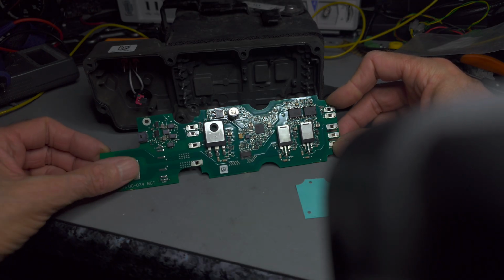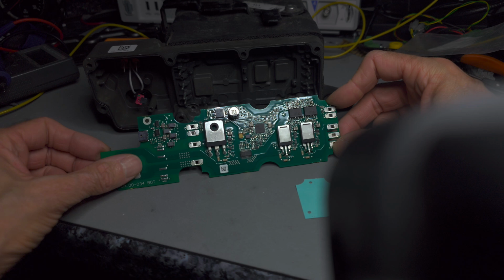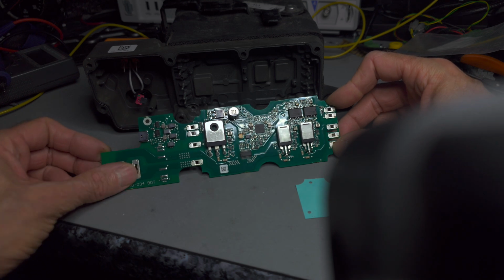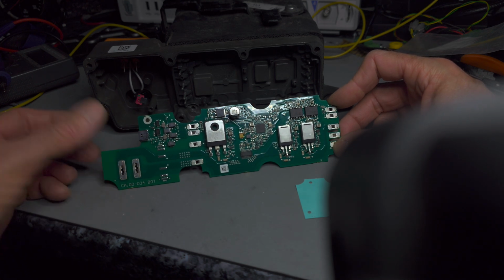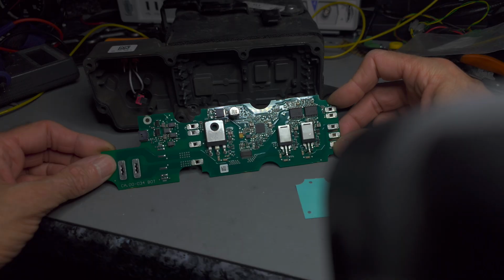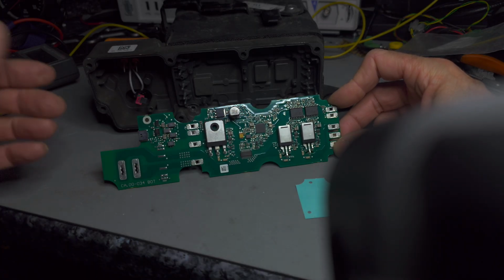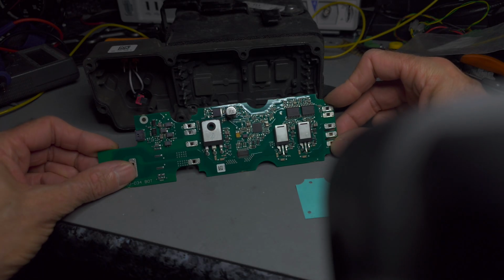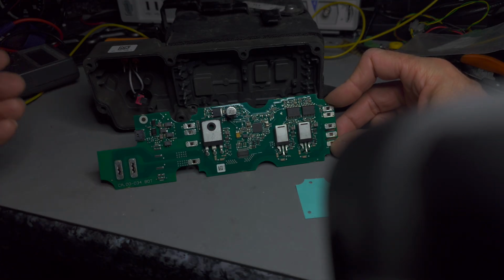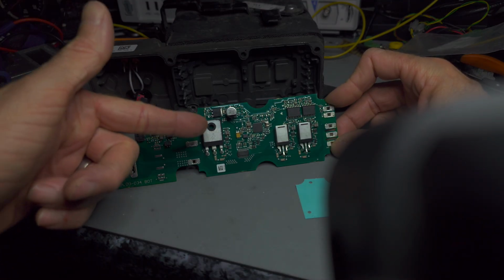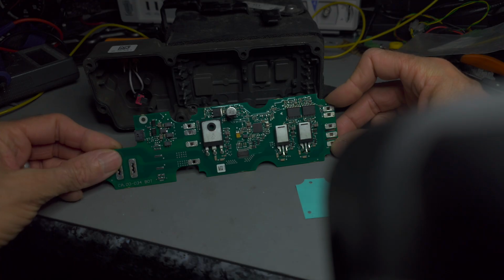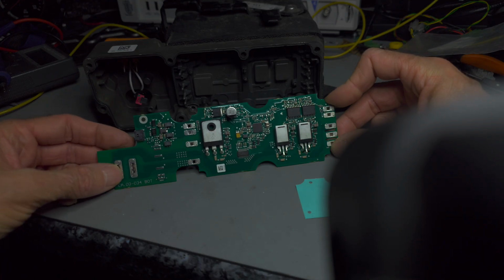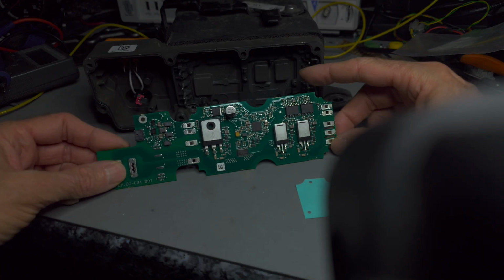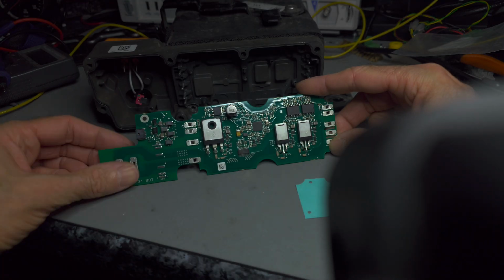So a small current - there's two switches in the battery. There's the main one which closes once the capacitors have been charged up, and there's a much smaller one that closes first, which allows a small regulated amount of current to flow to charge those capacitors up. Now, to stop that burning out due to a fault such as this one, there is a timeout imposed on how long that should take. If it takes too long, you get the error code you're seeing.